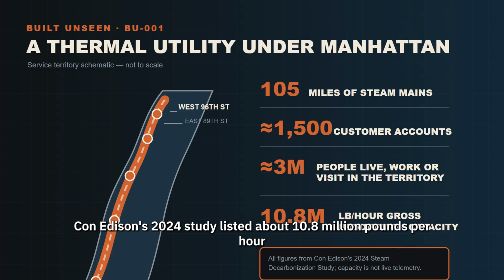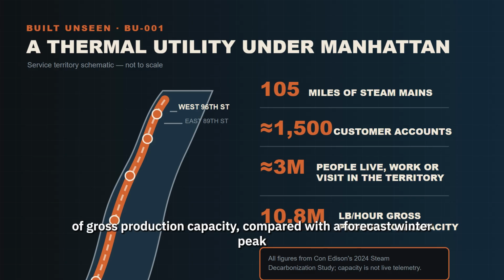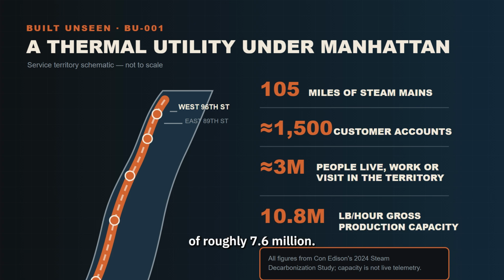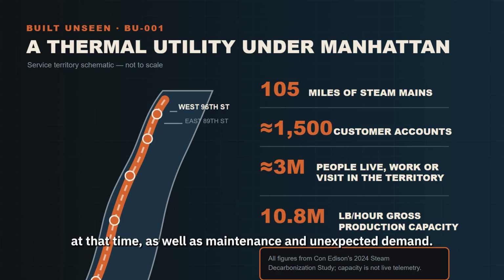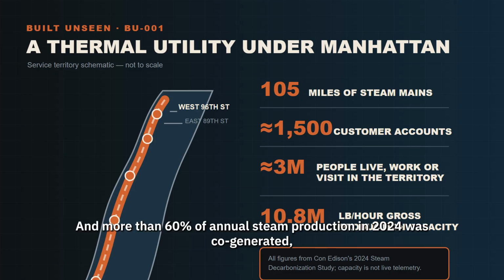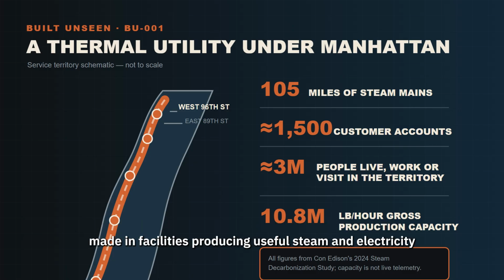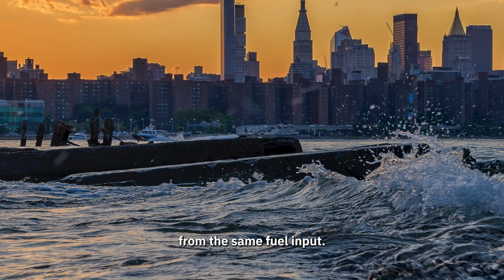Con Edison's 2024 study listed about 10.8 million pounds per hour of gross production capacity, compared with a forecast winter peak of roughly 7.6 million. The system is designed around an N-1 principle. Operators maintain enough quick response reserve to cover the loss of the largest steam unit operating at that time, as well as maintenance and unexpected demand. And more than 60% of annual steam production in 2024 was co-generated, made in facilities producing useful steam and electricity from the same fuel input.